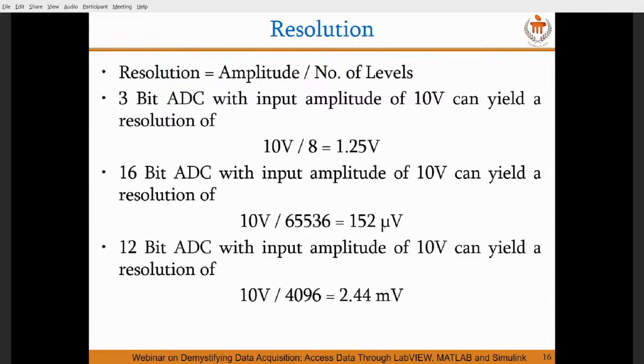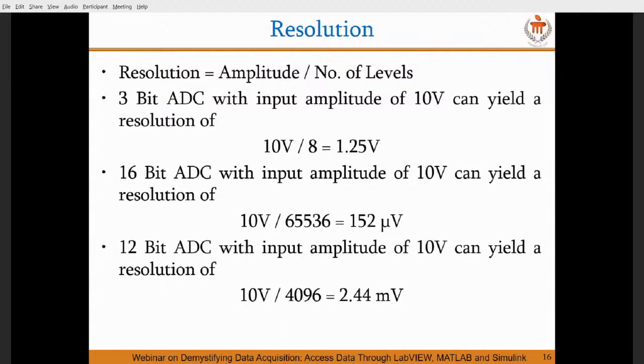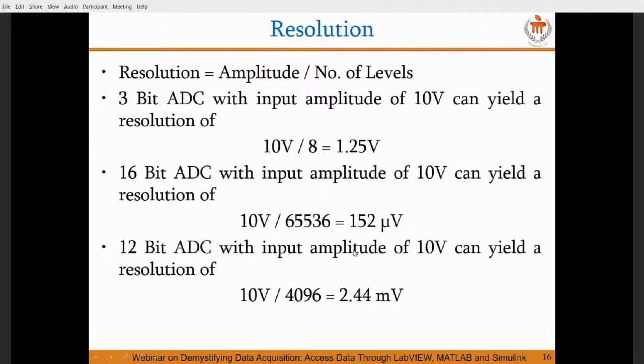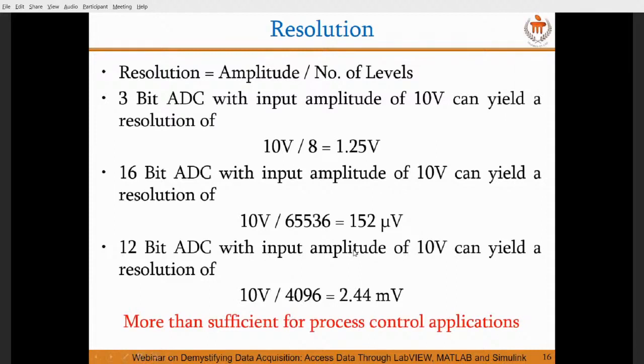Once the resolution is higher, there should be a higher clock frequency, so obviously the cost increases. With this basic understanding, you can select a proper data acquisition board for your use. You should be very clear with the process, with your range, your transmitter output, the minimum and highest frequency, and the minimum detectable voltage for your application. If you are thorough with this, you can select the corresponding ADCs and DAC ports. Usually 12-bit resolution is sufficiently high for process control applications.